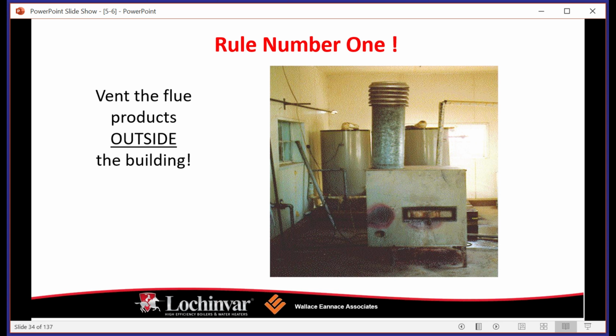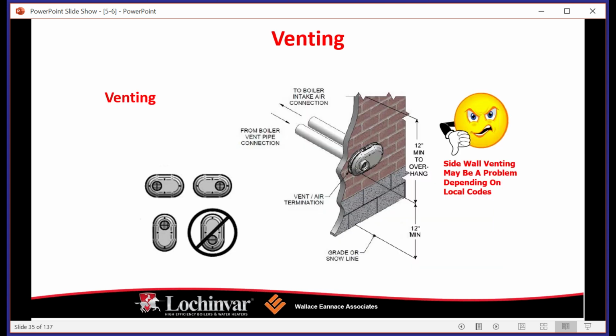Combustion venting is very important, and if you were to ask what's the number one thing that gets screwed up most reliably on an install, I would say it's probably venting. This slide is obviously a little extreme. Hopefully you never come across somebody venting their boiler inside an enclosed space, but flue gases contain carbon monoxide. Carbon monoxide is an odorless gas that is deadly if you breathe it in. So we want to make sure that we vent the flue products outside of the building. Very, very important.